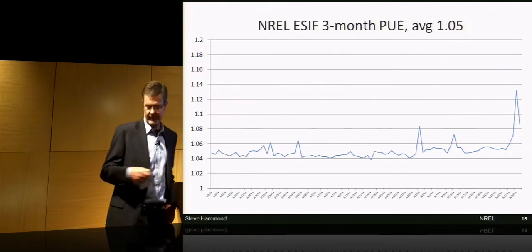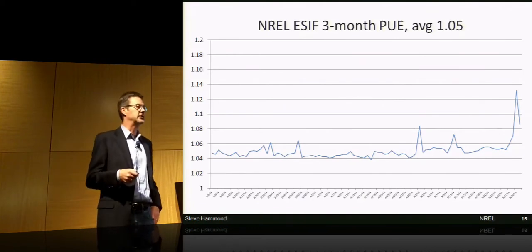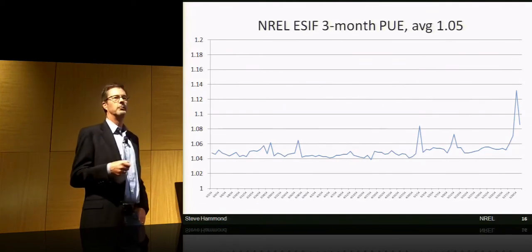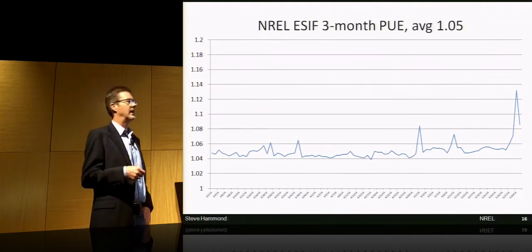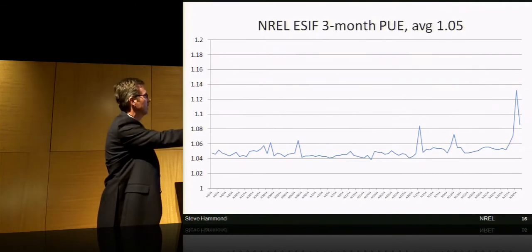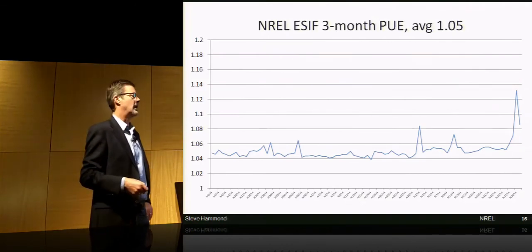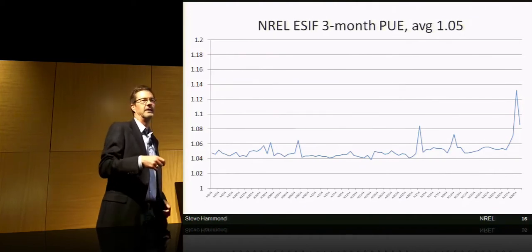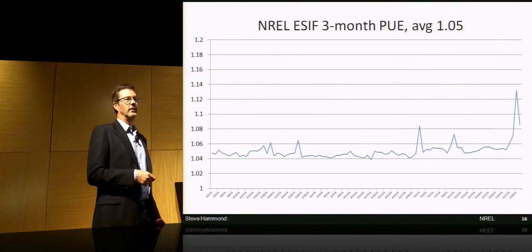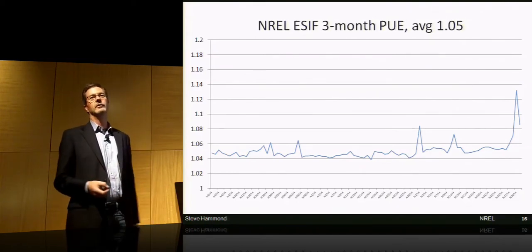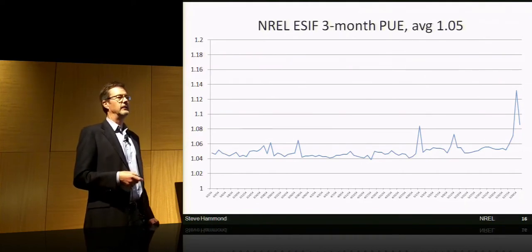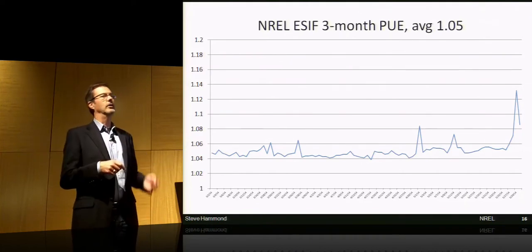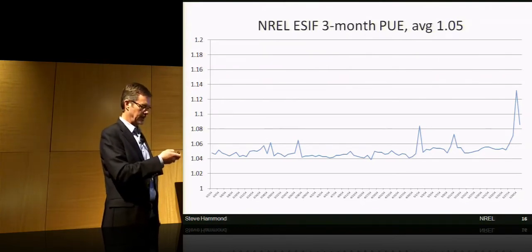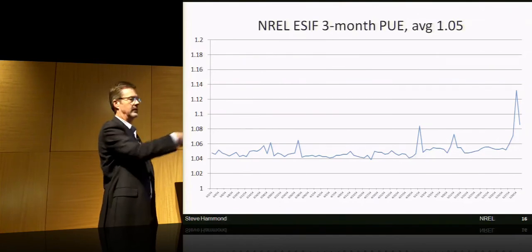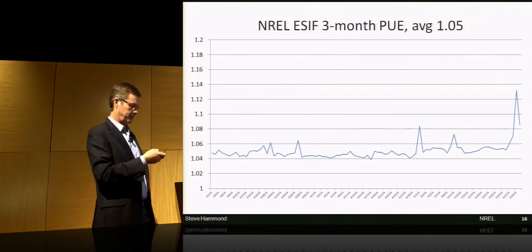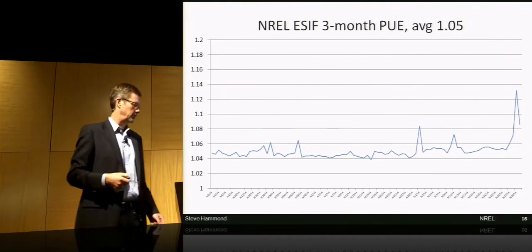I've just put up 3 months of PUE data, that's the power usage effectiveness. When I checked yesterday it was 1.044, but our trailing 3-month average is 1.05. Right here we had a facility-wide, campus-wide power outage, so we're not taking things out and saying that didn't count. That's actual data where we were shedding workload, but the infrastructure was still going. So even though our IT load went down, the infrastructure load stayed constant, which is the spike there, but more or less it just sits. The design point was 1.06 or better, so I think we're doing pretty well.